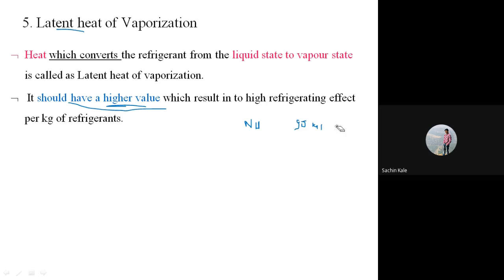So this is related to latent heat of vaporization. This table indicates all the thermodynamic properties of different refrigerants. The refrigerants selected here are R12, R22, R134A, 404A, 407A, ammonia, water, and carbon dioxide. And here we are differentiating those refrigerants depending upon various thermodynamic properties: boiling point temperature in degree centigrade, freezing point temperature in degree centigrade, latent heat of vaporization in kilojoule per kg, critical temperature in degree centigrade, critical pressure in bar, specific heat in kilojoule per mole, and COP.